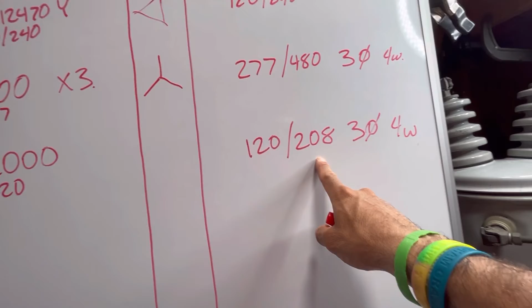Next question, can I fulfill my customer needs with these transformers, right? Again, there are going to be 3 transformers. This is the nameplate for all 3 of them. So can I fulfill this voltage with 3 of these? And the answer is yes. It will be a Y hookup. So 120, 120, 120, phase to phase, that distance right there is going to be 208, right?